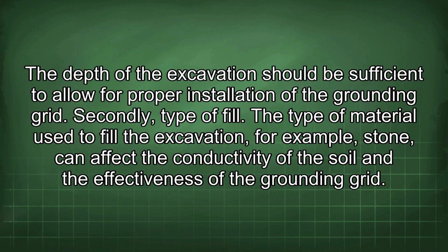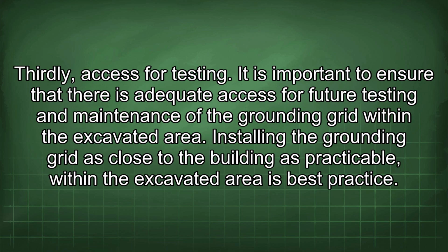The depth of the excavation should be sufficient to allow for proper installation of the grounding grid. Secondly, type of fill. The type of material used to fill the excavation, for example, stone, can affect the conductivity of the soil and the effectiveness of the grounding grid. Thirdly, access for testing. It is important to ensure that there is adequate access for future testing and maintenance of the grounding grid within the excavated area.